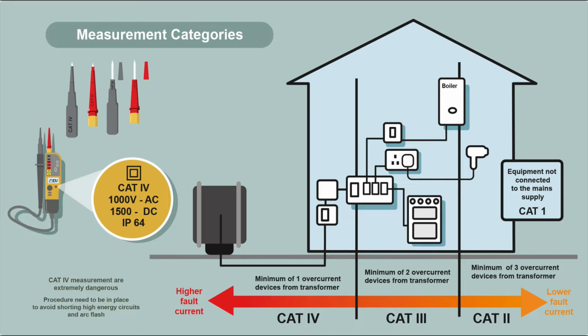When you are doing your safe isolation, you're testing that the circuits have been de-energised, but the voltage testers have to be capable of handling any voltage that could appear. You get different categories, Cat 4, Cat 3, Cat 2 and Cat 1. And the principle behind it is, if you imagine your house and you've got the transformer in the street, the further away you get from the transformer, the lower the category of tester that is required. The principle being the number of protective devices between what you're testing and the transformer.